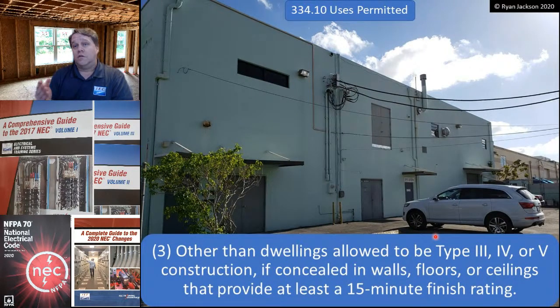For other than dwellings, so not one and two family, not multifamily, but commercial, industrial, institutional, other than dwelling units, they're allowed to be type 3, 4, or 5 construction, but you have to bury it in the walls or the floors or a ceiling that provides at least a 15-minute finish rating. Essentially, you have to conceal it, and you have to cover it with at least half-inch drywall, half-inch gypsum board. That'll give you a 15-minute finish rating.